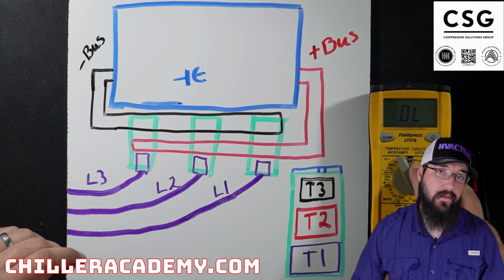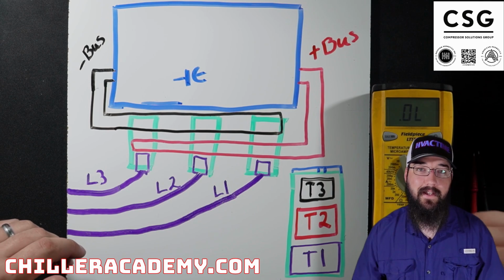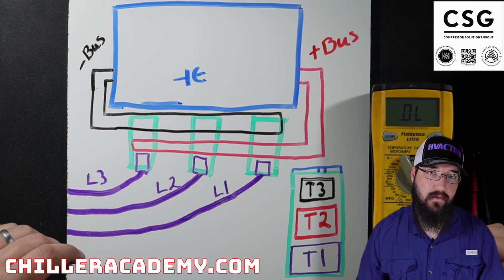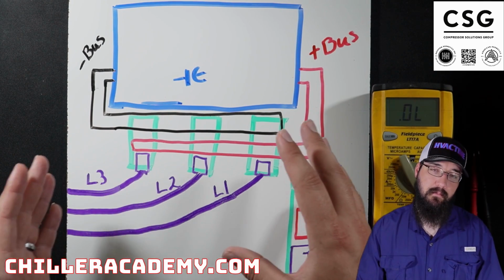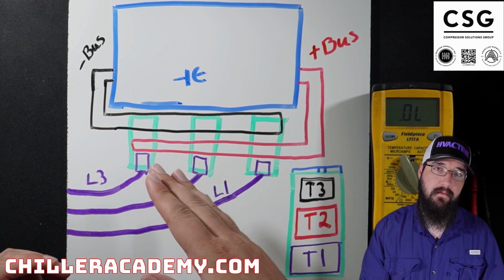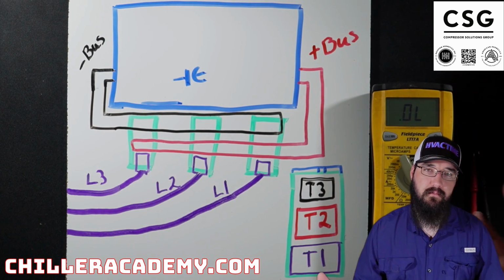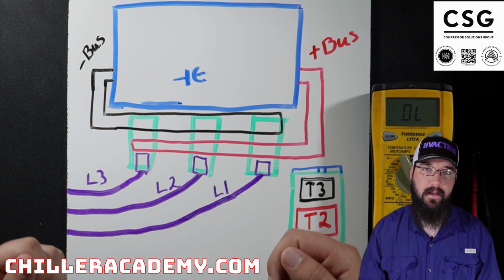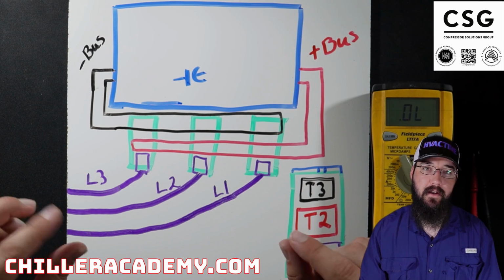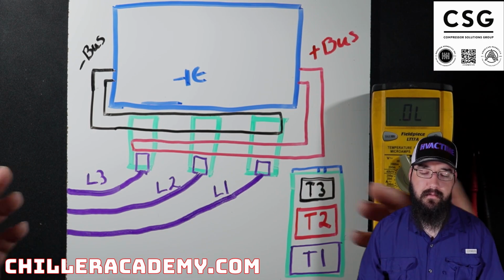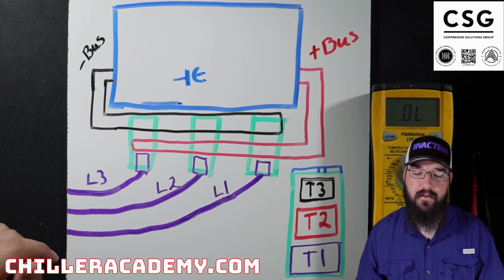To do that, you just want to set your meter to volts DC, at least a 600 volt scale. As the bleed resistors are taking the power off of the bus, you can literally sit there and watch that voltage drop. So if you wanted to just set your meter up with some clamps or alligator clip leads, you could quite literally watch it discharge.